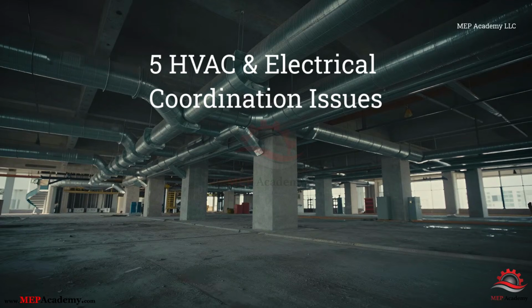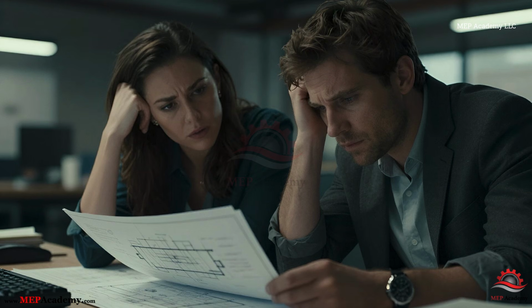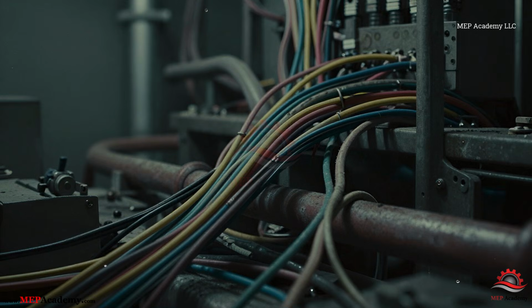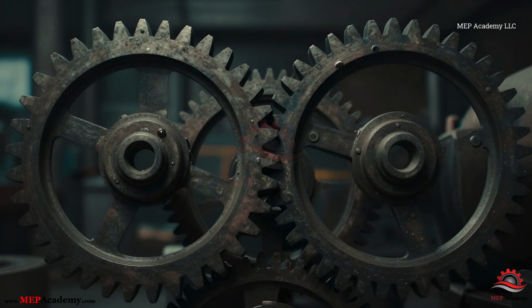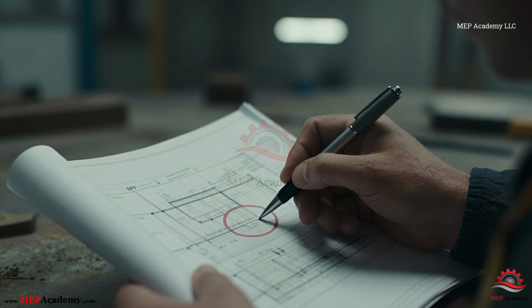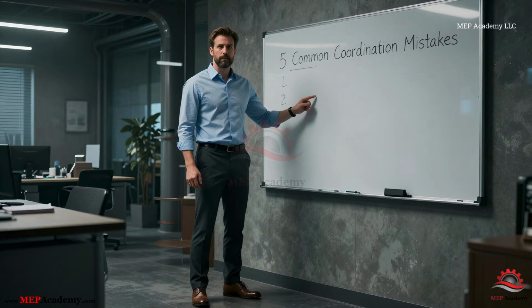On many commercial construction projects, HVAC and electrical systems install exactly as shown on the drawings. Inspections pass, and everything appears complete, until startup or final testing reveals that systems don't work together. At that point, the problem usually isn't installation, it's coordination. Small gaps between trades turn into RFIs, change orders, and delayed occupancy because responsibility for key items was never clearly defined. In this video, we'll walk through 5 of the most common coordination mistakes between HVAC and electrical contractors, why they happen, and how they can be prevented before construction even begins.